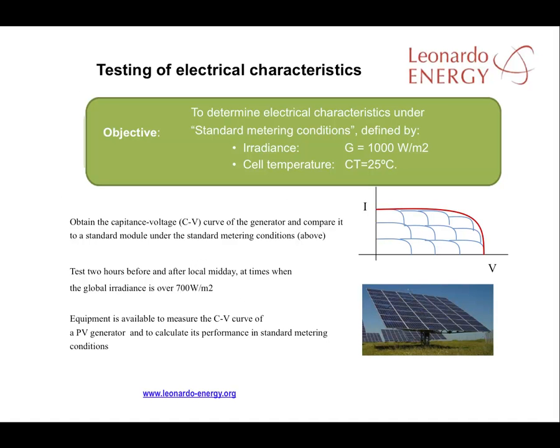The electrical characteristics of the PV generator should be checked against data for standard metering conditions — that's where the irradiance is one kilowatt per meter squared at a cell temperature of 25 degrees centigrade. By comparing the actual curve from the generator to the curve from that standard model, the performance of the PV generator can be established.